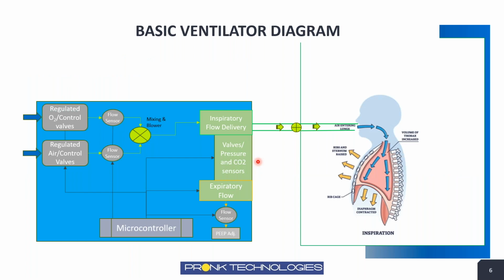Just a basic diagram of a ventilator, which I'm sure you're familiar with, outlines for us some of the critical things we need to make sure we're always servicing, even from the user level all the way through during PM service and repair. So this is a very rudimentary layout of the basic subsystems of a ventilator. You have, of course, your controls, your oxygen flow coming in from the outside with your control valves regulating that flow. Same with the air. You have your flow sensors for each particular channel, and then you have your mixing and your really precise blower that allow us to set an inspiratory flow value very precisely, set by the user, of course, to the levels that are needed for the patient to deliver the inspiratory flow to the patient.